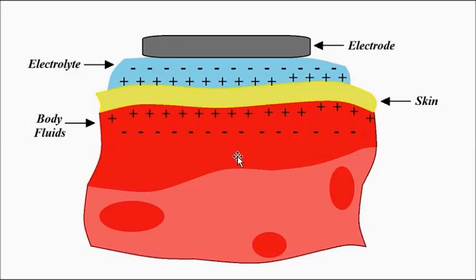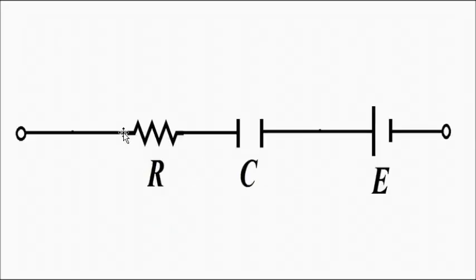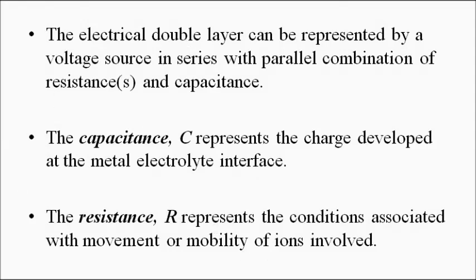The resistance represents the conditions associated with the migration of ions — the mobility of both positive and negative ions in the electrolyte and body fluids. It governs how easily the signal can migrate and penetrate through the electrolyte-skin interface and reach the electrode. C is the capacitance associated with the charge layer, R is the resistance associated with ion mobility, and E is the contact potential. To simplify, we can represent it as a resistor in series with a capacitor and then the contact potential.